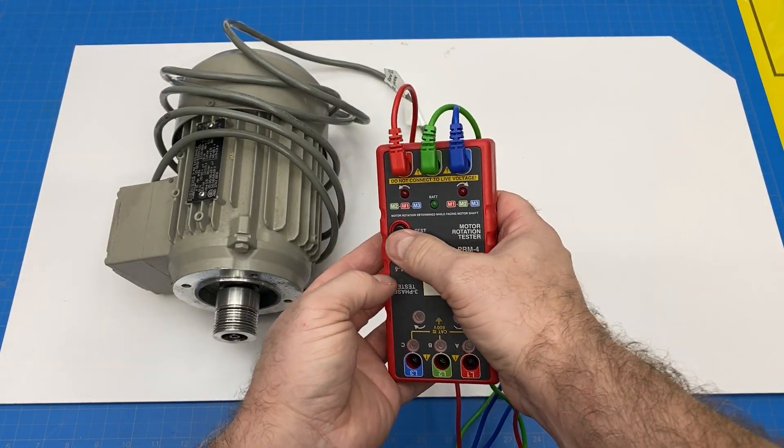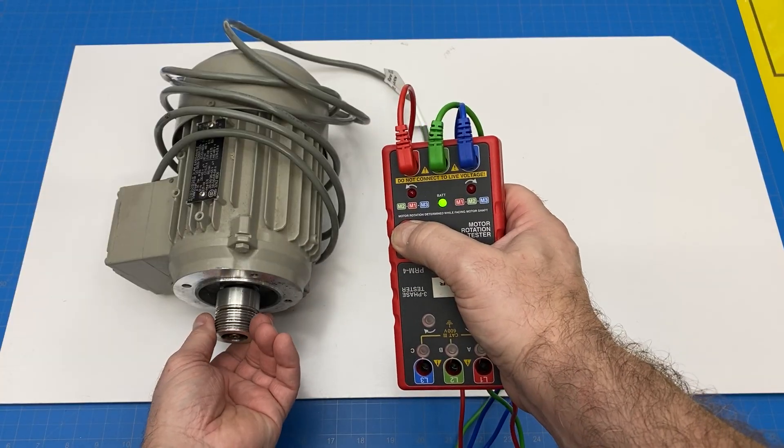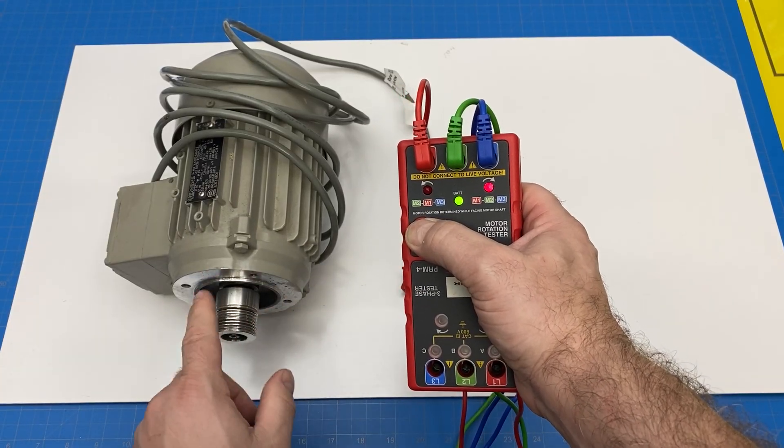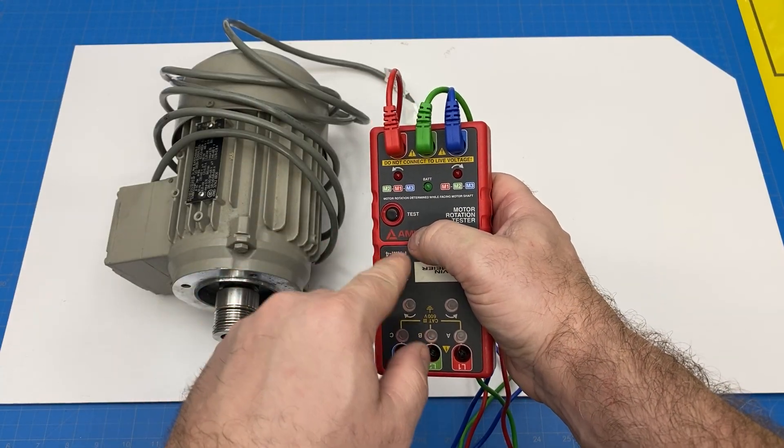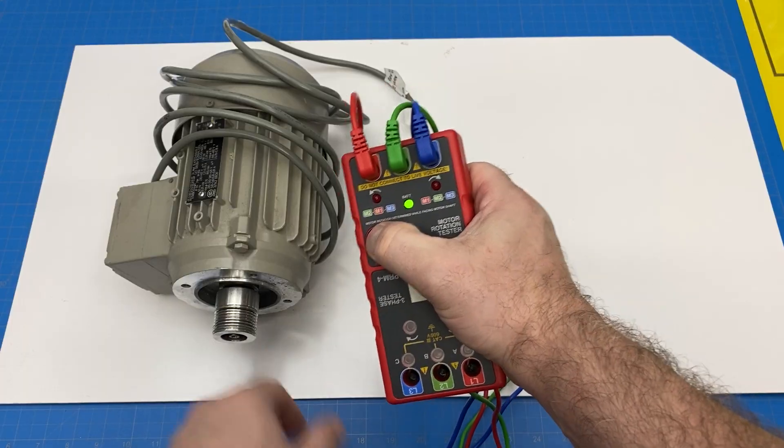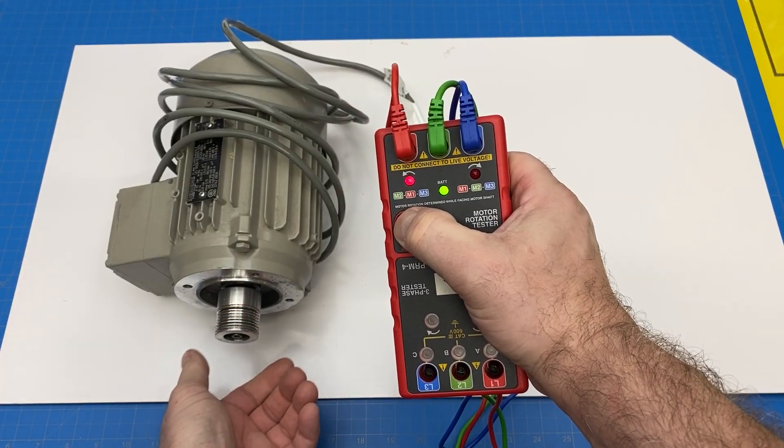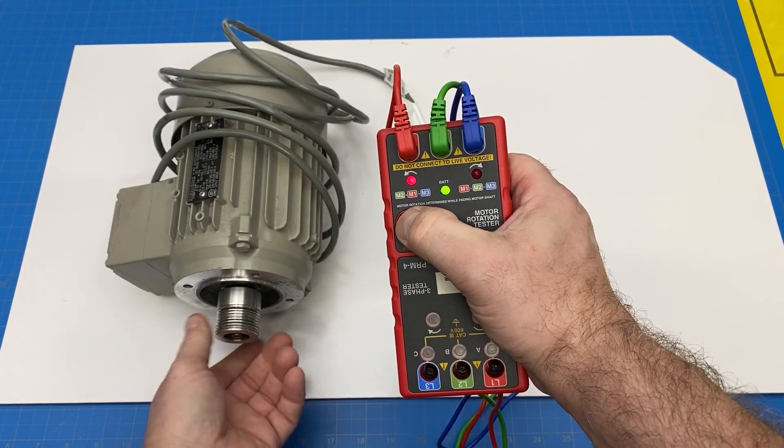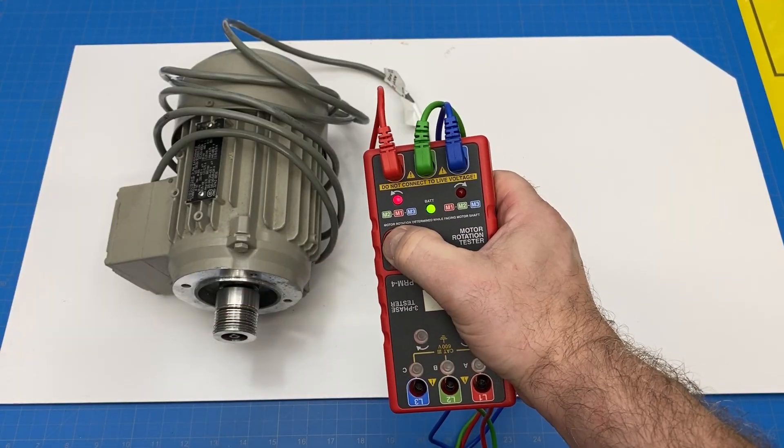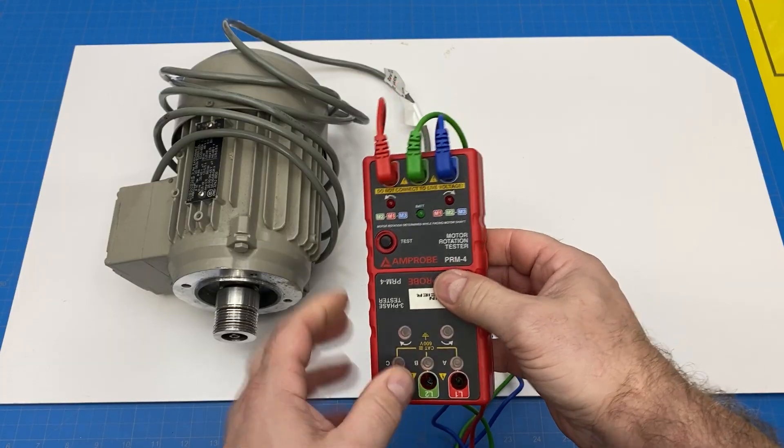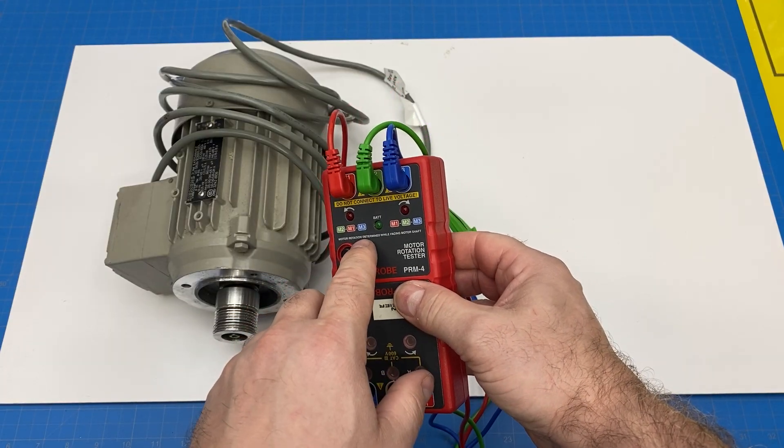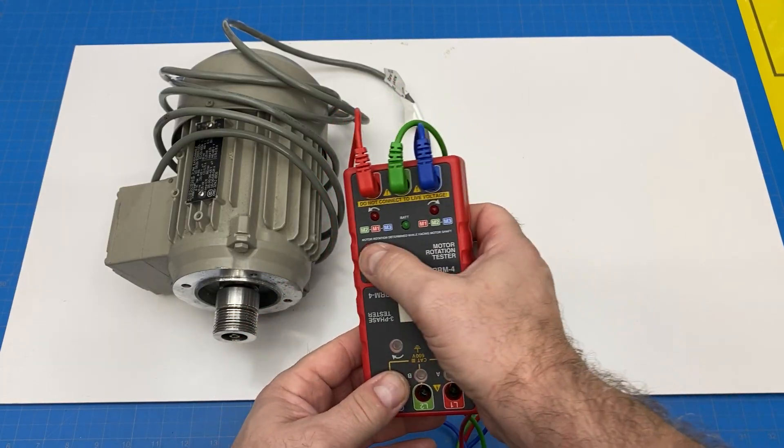Then we press the test button and turn the shaft of the motor. As we can see here, when I turn the shaft clockwise I get a clockwise rotation, so this one's correct. To test the other direction, let go, press it again, and then turn. If I don't let go and then change rotation, it won't actually change here, but that's okay. The note says the rotation is facing the shaft, so this would be correct.